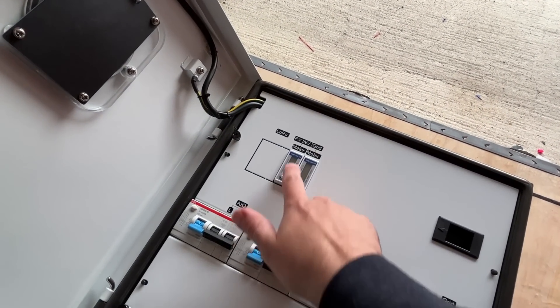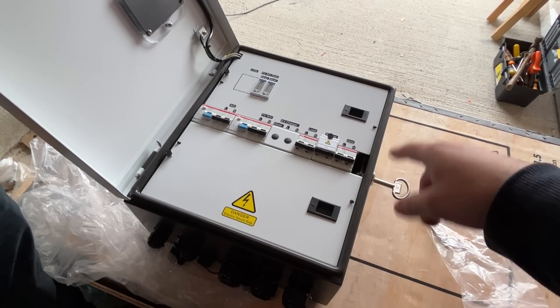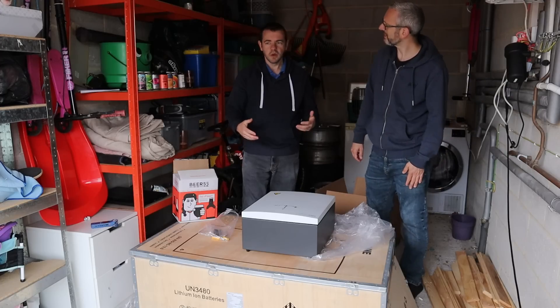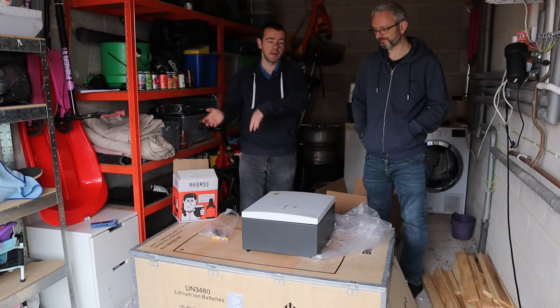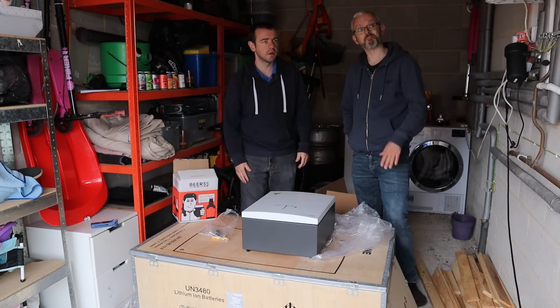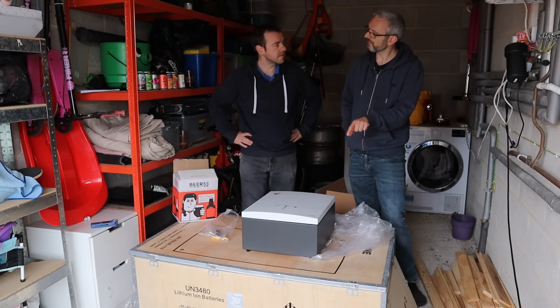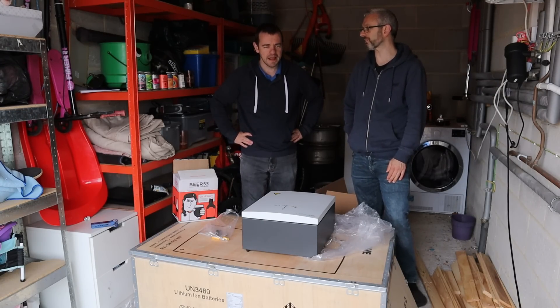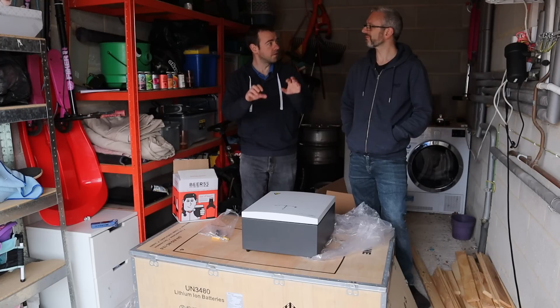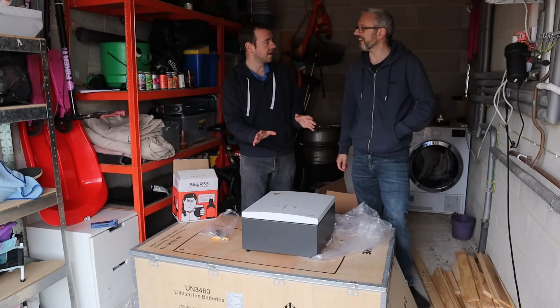So we've got some GEM 120 CTs. Do you think other British manufacturers will be looking at this going - write down what it does? I think so, they've probably already bought one. The finish is nice, no sharp edges. We'll do the proper install and mimic a power cut by switching the fuse off to see what happens. If the man maths has worked, this is the right thing to buy first. If you can do solar and battery, great, but if you can only do one - and they're roughly similar price, though this is more expensive - it's a 13.5kWh battery that's going to more than do your day in terms of what you're using.